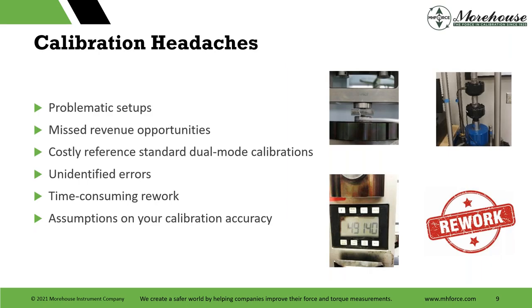So some of the headaches you may have are problematic setups, missed revenue opportunities, and costly reference standard dual mode calibration. What that means is some machines have reference standards that are used in both tension and compression. When that happens, you need them calibrated in both tension and compression. You also need to really exercise those standards numerous times. Sometimes two exercise cycles are not enough, and you need three, four, or five exercise cycles when switching modes. So that's a little bit of the conveniences. Everything is in one setup.